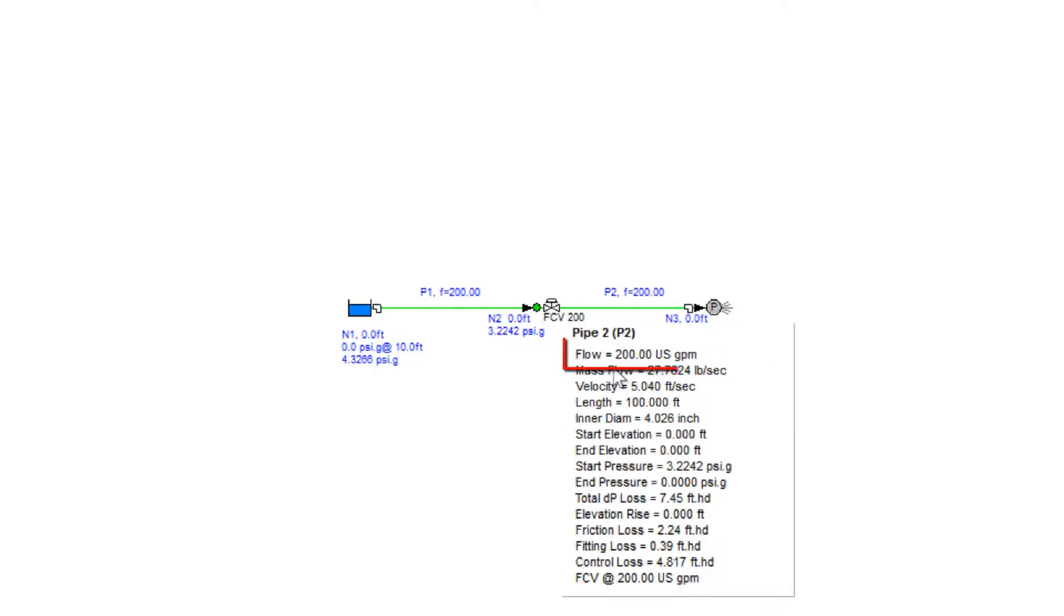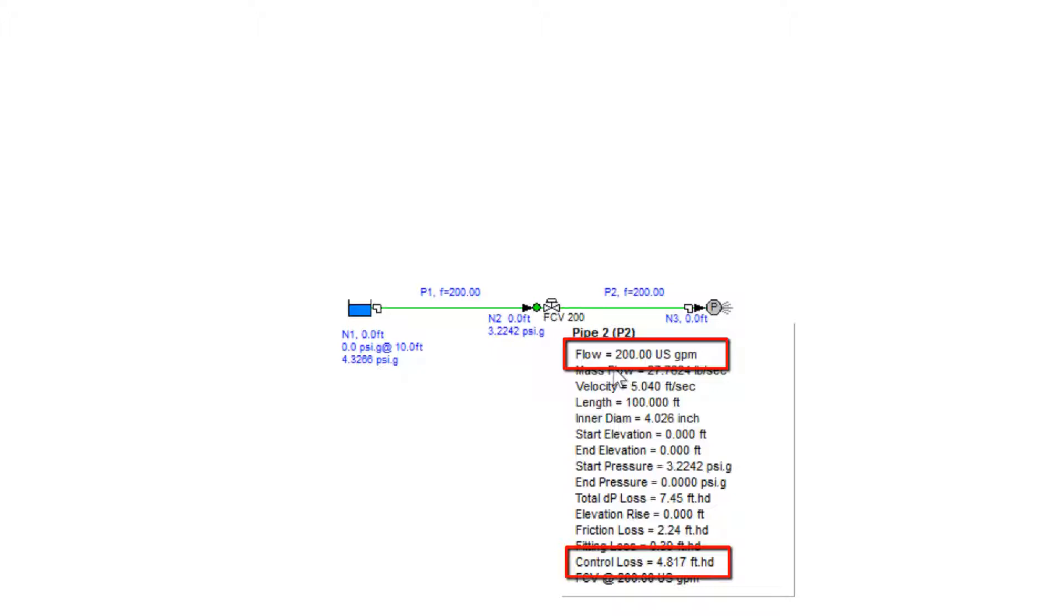We can also see that there has been a control loss added of just over 4.8 feet of head, and this is the loss that the flow control valve has introduced into the system in order to control the flow at 200 US gallons per minute.